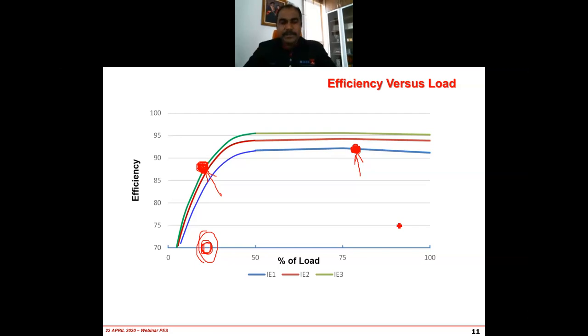Correct. So this is possible, and it always happens in industry, because most of the time when we go into the industry, the engineers are not aware of the loading factor of the motor at the moment. All the while they see, okay, the motor is running fine, but they are not sure whether the motor is driving 75% or 50% load. They have no idea about it. So if you just blindly convert it to IE2, IE3, you don't see so much saving, or probably no saving at all. Then how are you going to justify the additional cost that you have spent to buy the motor? You cannot justify that.